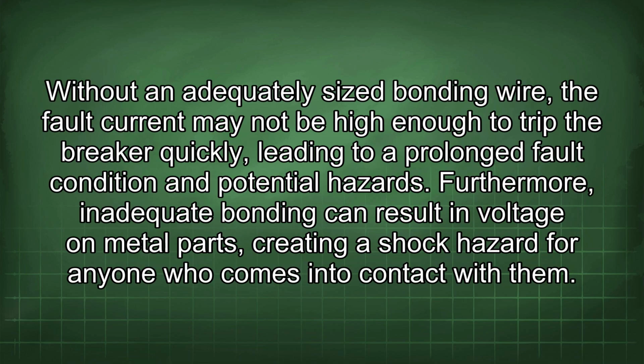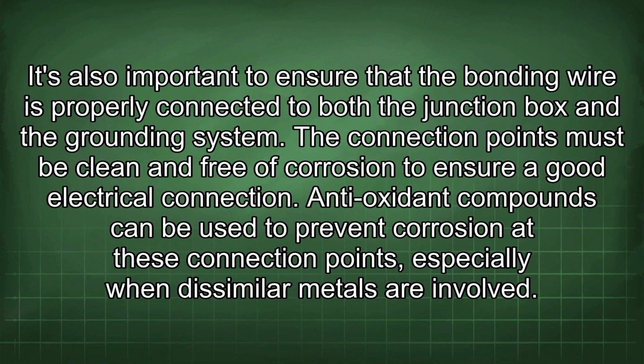Without an adequately sized bonding wire, the fault current may not be high enough to trip the breaker quickly, leading to a prolonged fault condition and potential hazards. Furthermore, inadequate bonding can result in voltage on metal parts, creating a shock hazard for anyone who comes into contact with them. It's also important to ensure that the bonding wire is properly connected to both the junction box and the grounding system. The connection points must be clean and free of corrosion to ensure a good electrical connection. Antioxidant compounds can be used to prevent corrosion at these connection points, especially when dissimilar metals are involved.